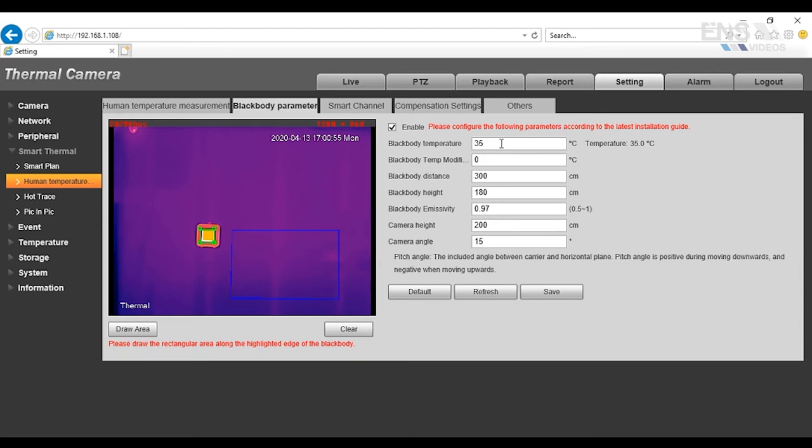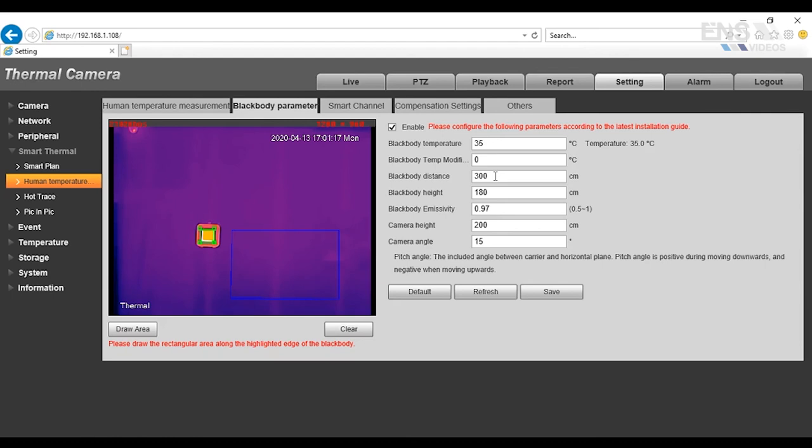The black body distance is the distance from the black body to the camera, which is recommended to be 3 meters for accuracy. Now, the 300 centimeters is 3 meters, so 100 centimeters is 1 meter. So when you set it on a tripod, the black body and the camera, you want to measure the distance from the center pole of the black body to the center pole of the camera. That's where you'll get your 300 centimeters or your 3 meters.